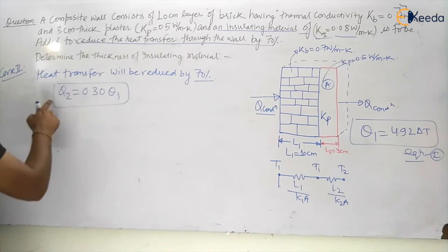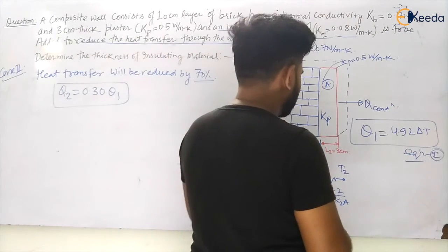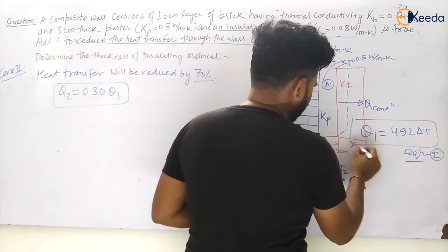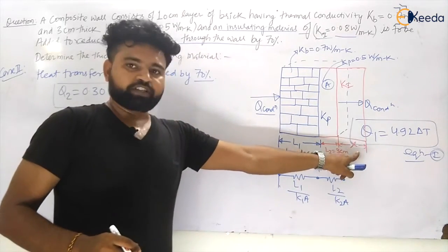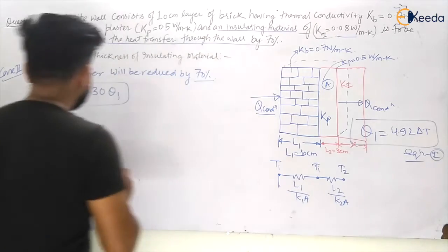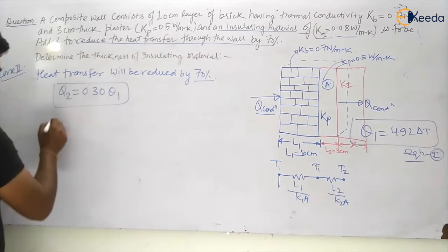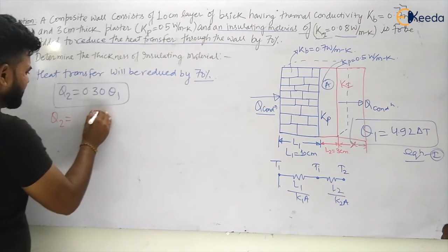Okay. So can we calculate the heat transfer when we are adding an insulating material here? Yes, let us say I am adding an insulating material here and there will be some heat transfer through it. So let us say K insulation is there and I have to calculate X. So the thickness of insulation is X. So your Q2 will be given by delta T by R effective.